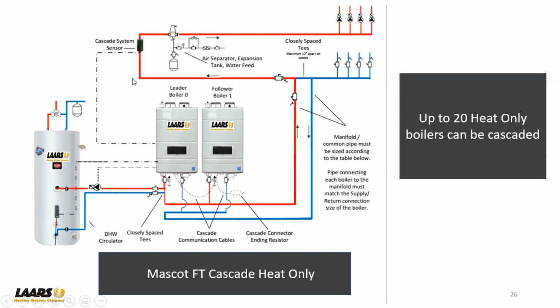Okay. Now, you could also potentially tie it off as another zone, land that aquastat at the boiler. But what will happen is the whole system then goes right back to 180, and there goes your outdoor reset curve. So primary, secondary piping, that's where you want your indirect tanks.